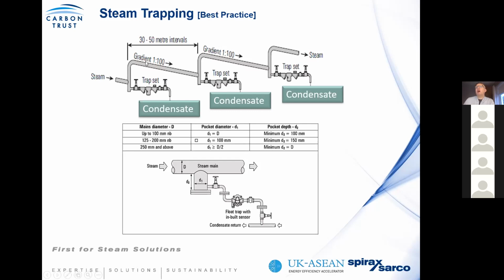So you should have on a distribution system at least 30 to 50 meter intervals a steam trap station. And our engineers within a region would always be advocating, you need effective trapping. There's reasons for this, because if you don't remove the condensate effectively, you create water hammer issues. If you have water hammer issues, you have very poor heat transfer, and you end up damaging end plant or distribution systems, like which was shown in the previous slide.